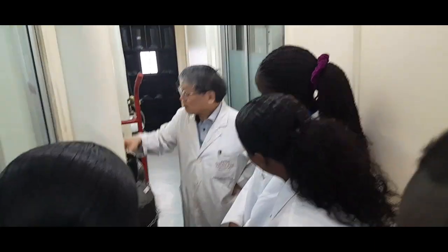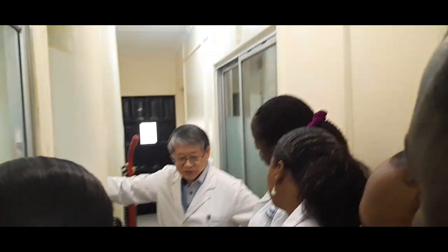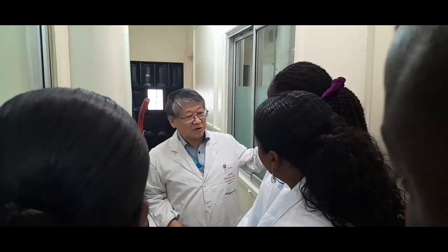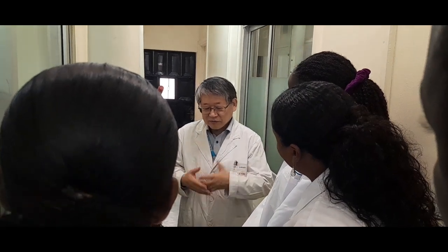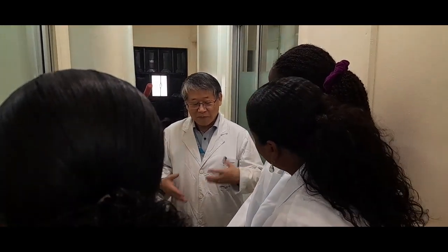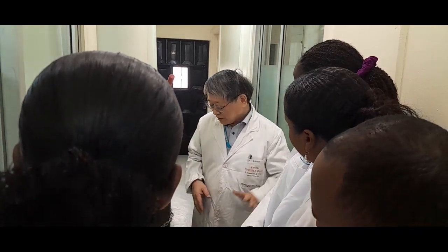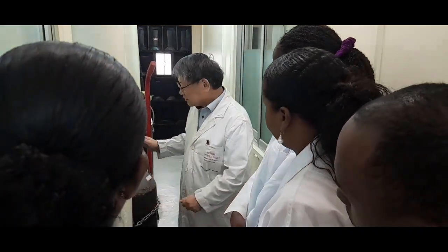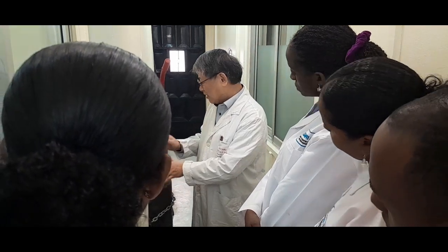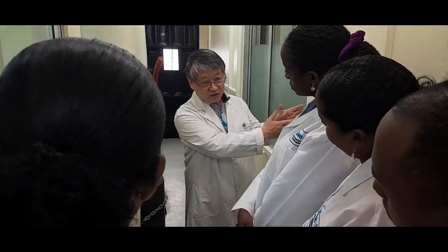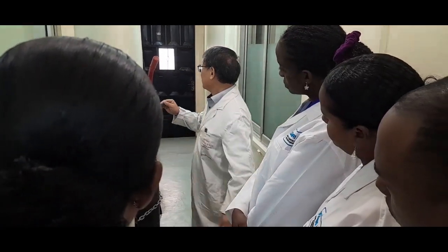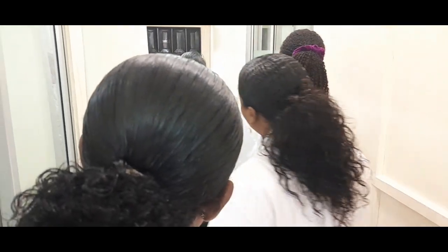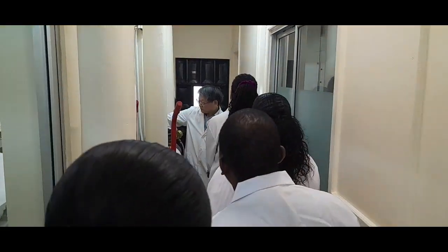I think for the cell culture room it's okay, but for the P2 laboratory, with field samples, clinical samples, or pathogen handling, there's a possibility of contamination from the cylinder.